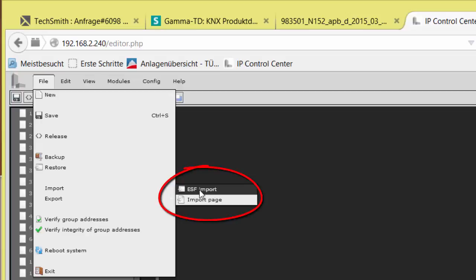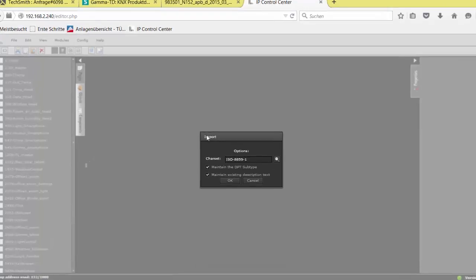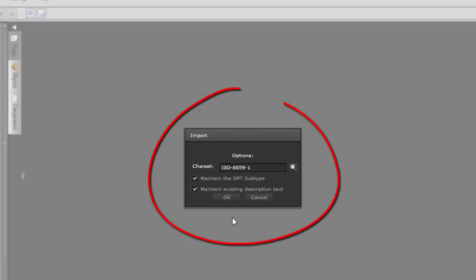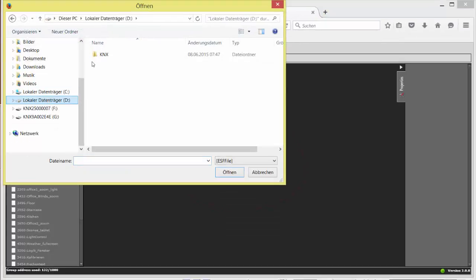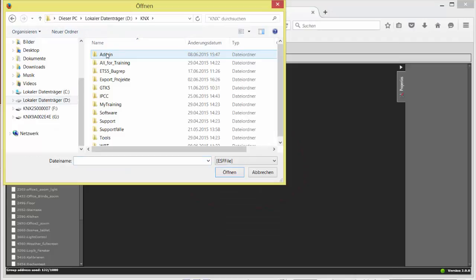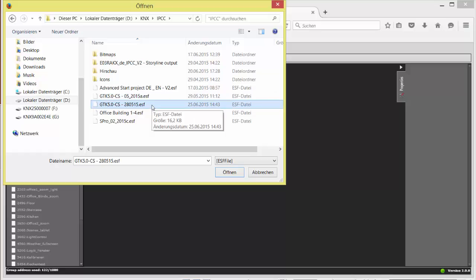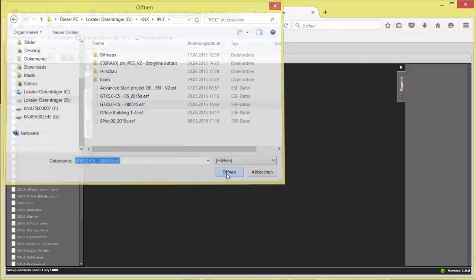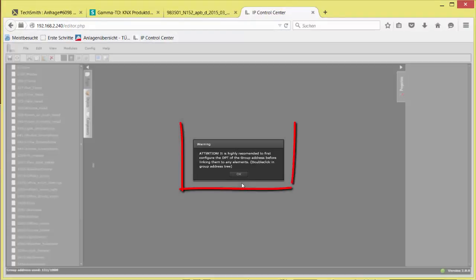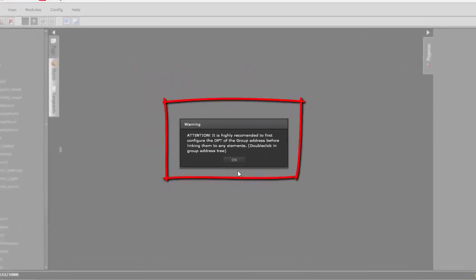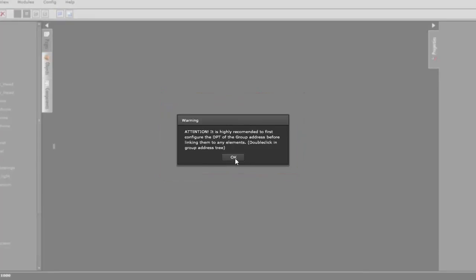Under File, ESF Import, the file browser of the commissioning PC is opened. After you have confirmed an info dialog about character code setting and text labels of the objects and group addresses, navigate to the directory where you have saved the ESF file before. Select it and click on Open. The upload is now running. The following possible warning about the checking of the data point types must also be positively confirmed.